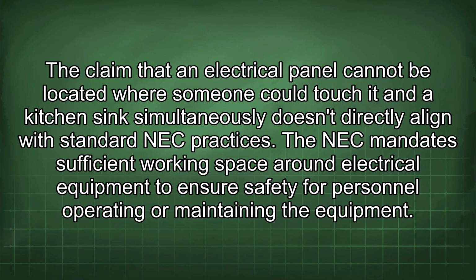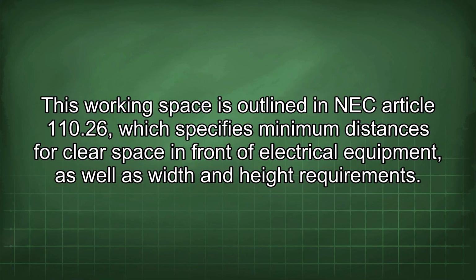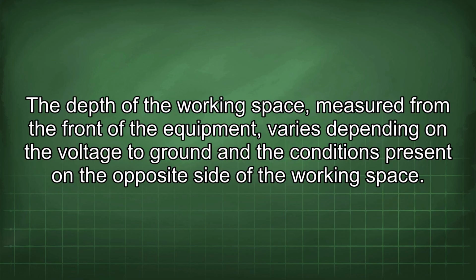The NEC mandates sufficient working space around electrical equipment to ensure safety for personnel operating or maintaining the equipment. This working space is outlined in NEC Article 110.26, which specifies minimum distances for clear space in front of electrical equipment, as well as width and height requirements. The depth of the working space, measured from the front of the equipment, varies depending on the voltage to ground and the conditions present on the opposite side of the working space.